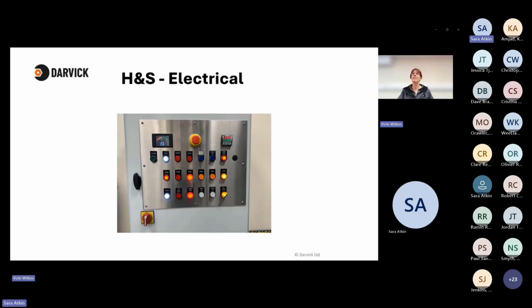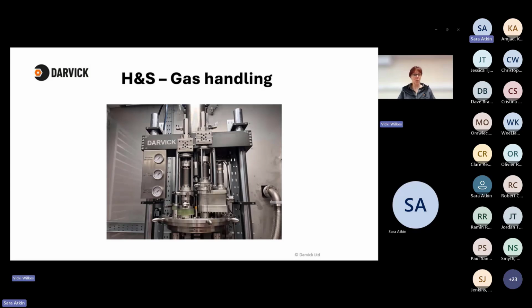But it's all the additional research and development that you have to do when you're validating a machine to work with these components that are safe for use with hydrogen. So if we do get a spark, if for some reason we have a metallic component that fails when we're testing it, because we're testing it to destruction, we want to ensure that there's not enough hydrogen to ignite. This brings us on to gas handling, and gas handling is basically extraction, purging and venting. When you're using hydrogen, you have to make sure that before you introduce hydrogen into a system you have purged it. You've got rid of all the oxygen in there. As we said, oxygen is not what you want for a fire.